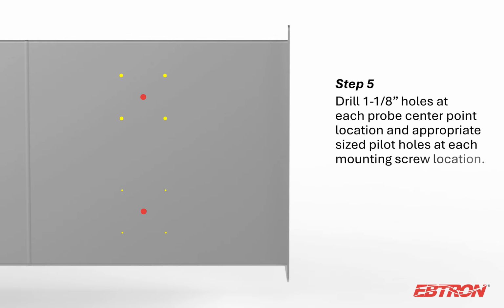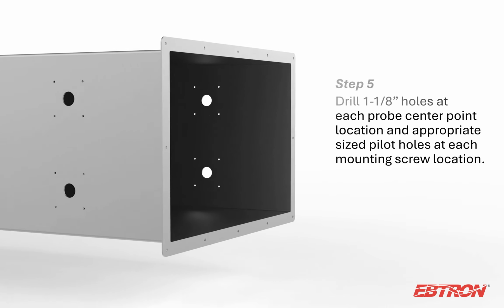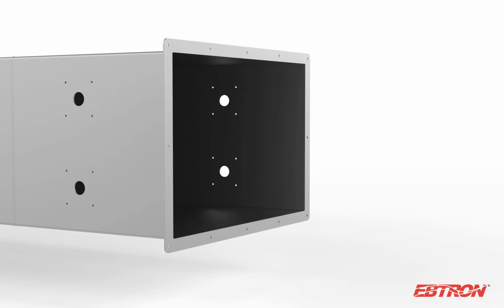With all the insertion and mounting screw locations marked, we can now drill a 1 1/8 inch hole at each probe center point, as well as appropriately sized pilot holes at each of the mounting screw locations. We're now ready to install the probes into the duct or opening.